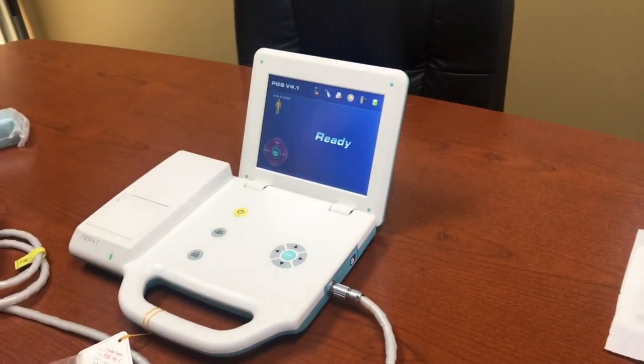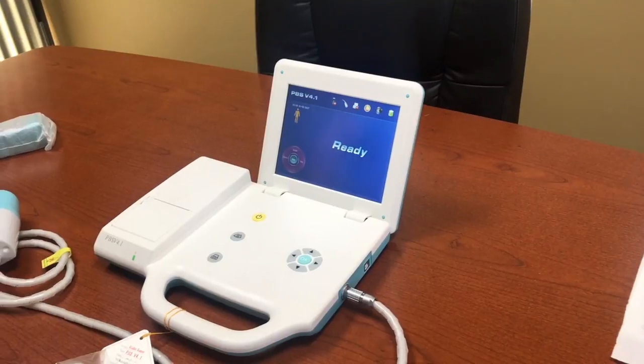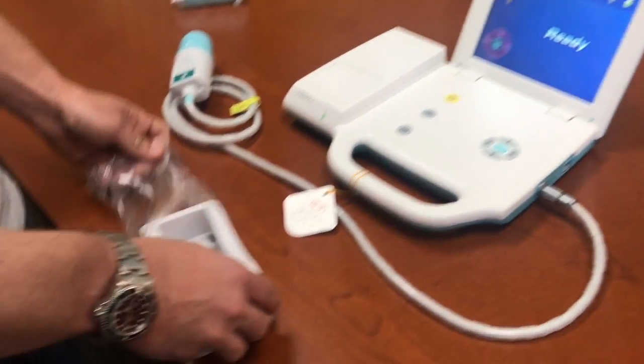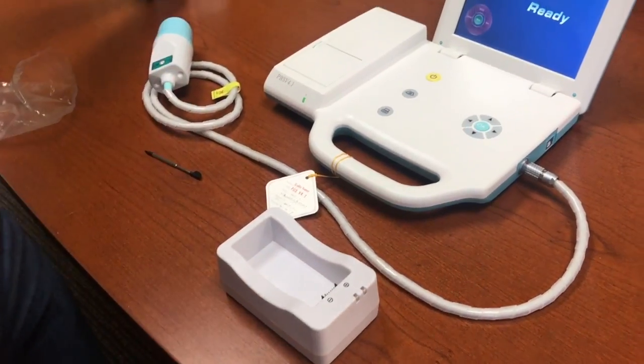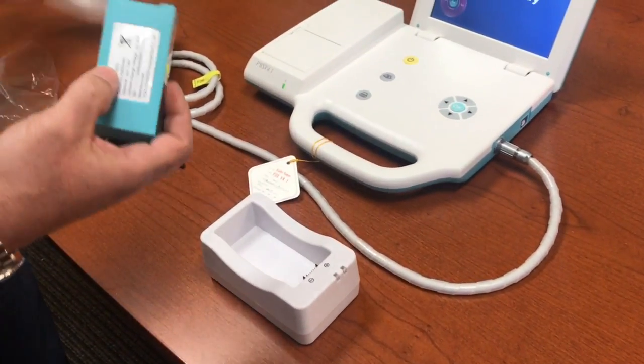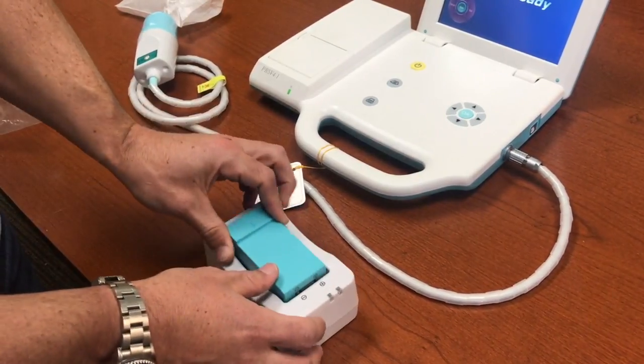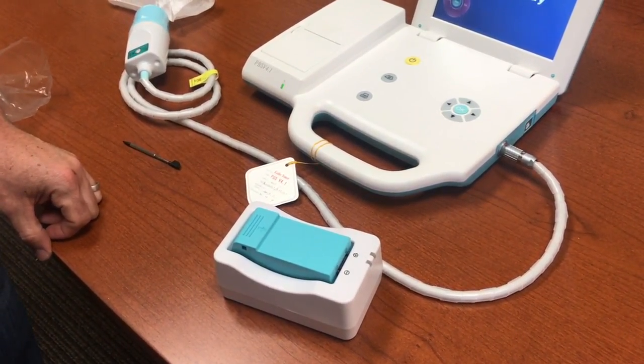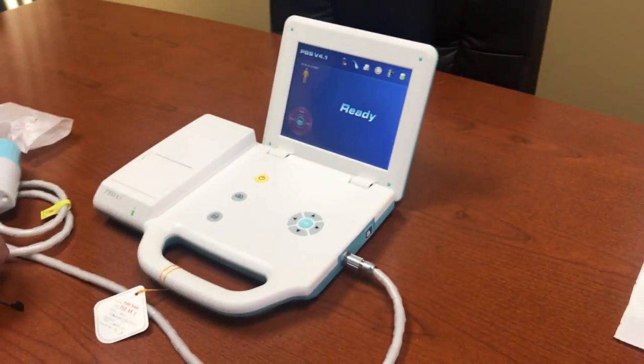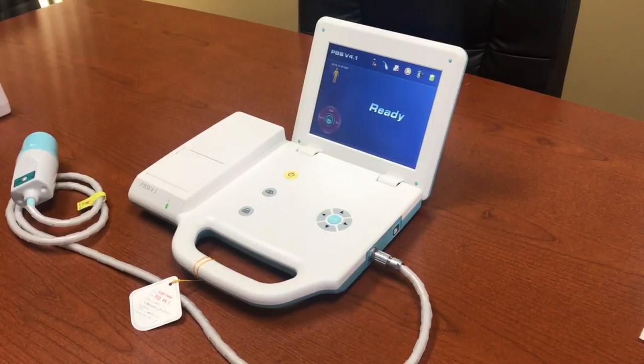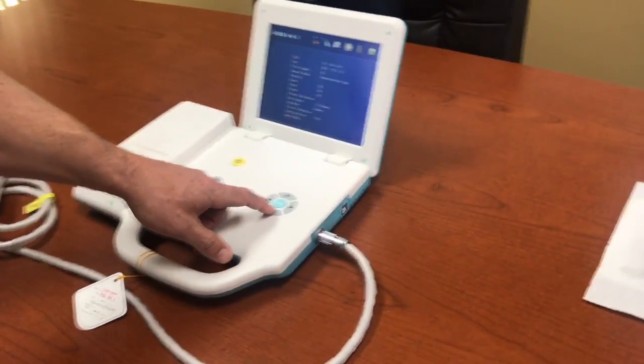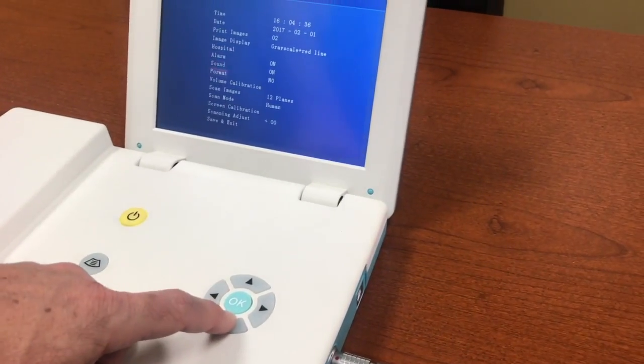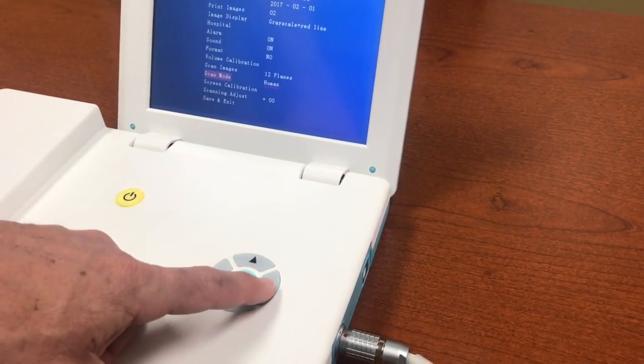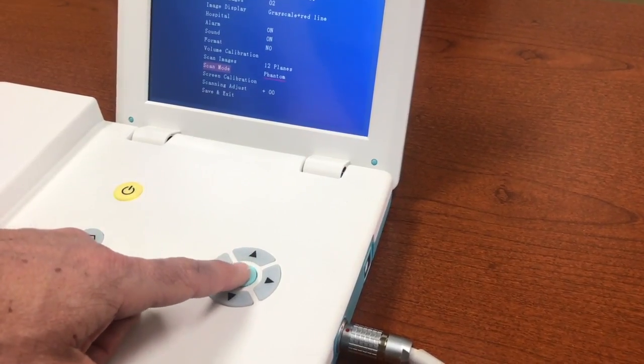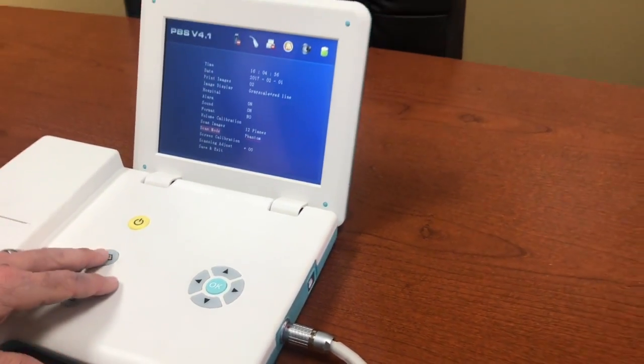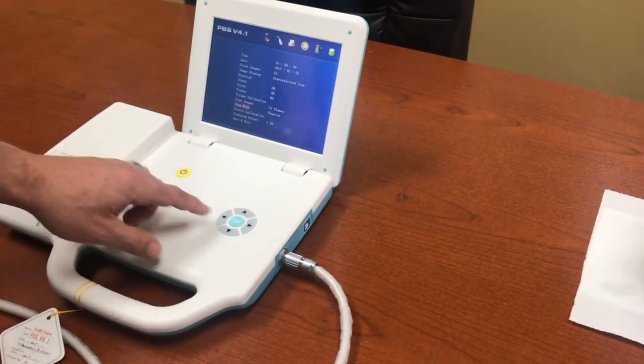As I mentioned previously, this model does not include an AC charger that you plug into the rear of the unit. You would simply swap the battery, and this is what the charger looks like. And again, just like placing a battery in the unit, you would match these two up and drop it into place and it would charge. Since we already have a charged battery, let's go ahead and perform a simulated test. I am going to go into the menu and scroll down into scan mode and change it from human to phantom, which is what we'll be using to simulate our bladder. And then we'll press OK and save and exit.